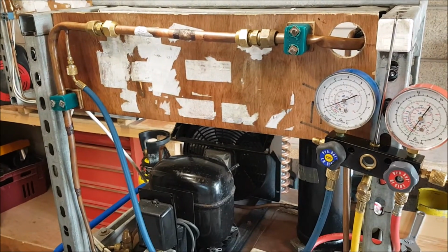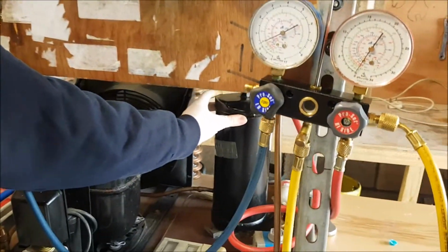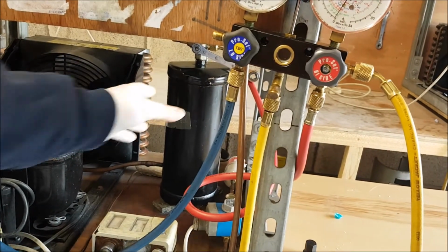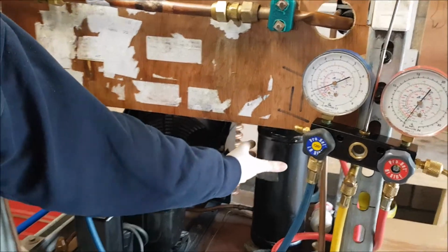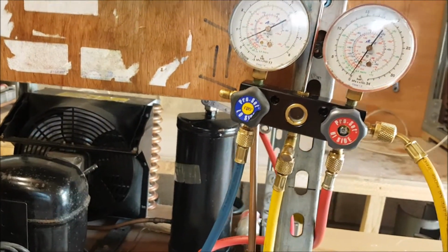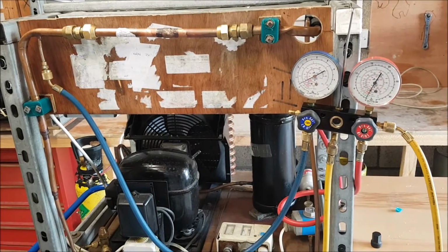So there are occasions when all that is necessary is to carry out a pump down of the refrigerant into the high side of the system. This is only possible where you have a liquid receiver. By pumping down the refrigerant into the high side of the system, we are then able to carry out whatever remedial repairs we need.